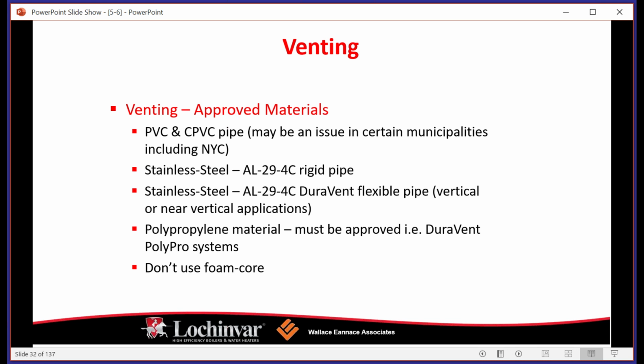What we're doing is we're capturing latent heat in the heat exchanger rather than letting the boiler gases change state in the flue pipe. So because we're capturing the energy in the heat exchanger, our flue gases are typically very low. Ordinarily, you're not going to see flue gases above 140 degrees, and even that's a little high. So we're able to use PVC, CPVC. This is, again, subject to your local regulatory. In the New York City 5-borough area, PVC is not allowed. I would expect that we're going to see that trend in major metro areas across the United States, depending on where you guys are listening from.